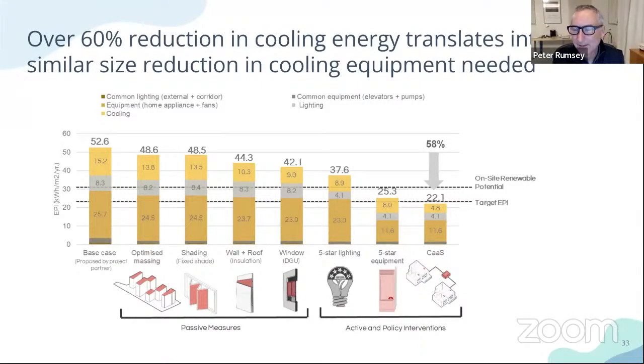So remember what I said, cooling is smaller. And if you have a building with a generator, most buildings do now, the generator is smaller. Even if you don't have a generator, the electrical equipment is smaller: the transformers, the electrical wires, the service from the utility, all that's smaller. So very compelling, very nicely done.